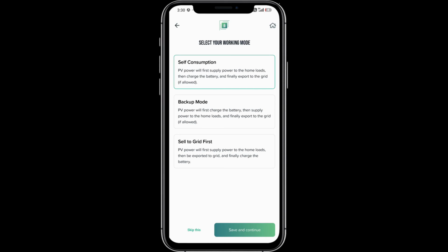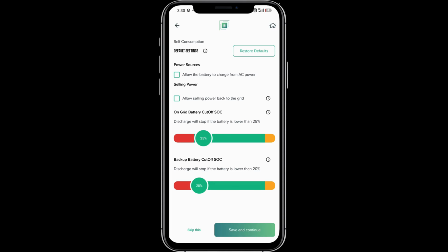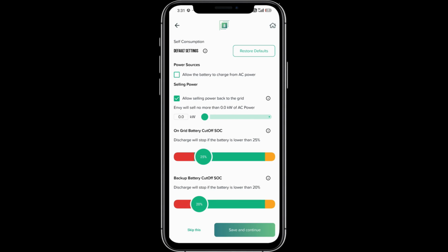Select the application based on your energy needs. And here at Fortress Power, we already provide the preset parameters for each operating mode, making it easier to apply the appropriate settings. On the next page, you will confirm these settings and adjust any parameters as needed. You can set the battery on-grid cutoff, which determines the state of charge at which the system switches the load from battery to the grid. You can also configure the off-grid cutoff, which means that when the battery reaches this SOC level, the inverter will stop supplying power to the load port, and this value is typically set at 20%. Finally, you have the option to enable grid charging based on the battery state of charge, as well as activating the export to grid function.